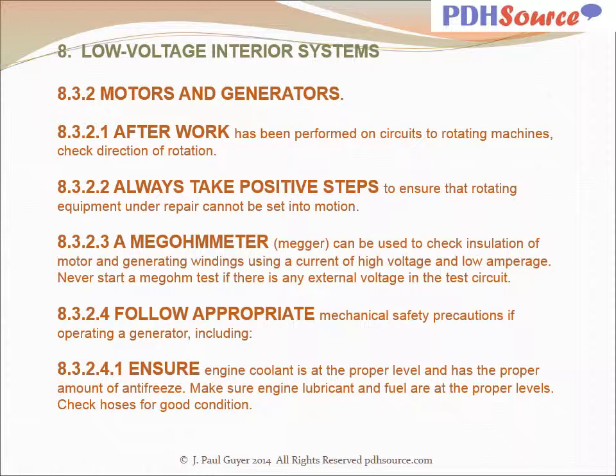With regard to motors and generators, after work has been performed on circuits to rotating machines, check direction of rotation. Always take positive steps to ensure that rotating equipment under repair cannot be set into motion. A megohmmeter, a megger, can be used to check insulation of motor and generating windings using a current of high voltage and low amperage. Never start a megohm test if there is any external voltage in the test circuit.